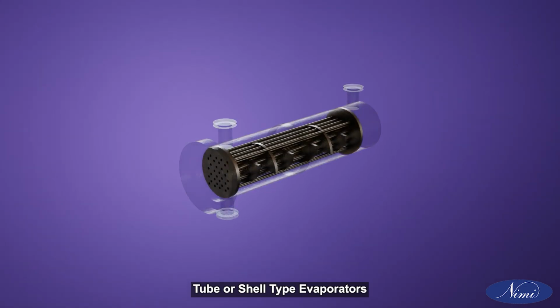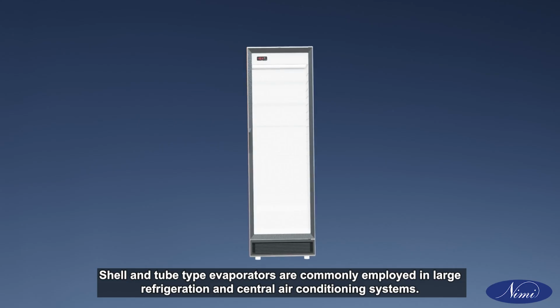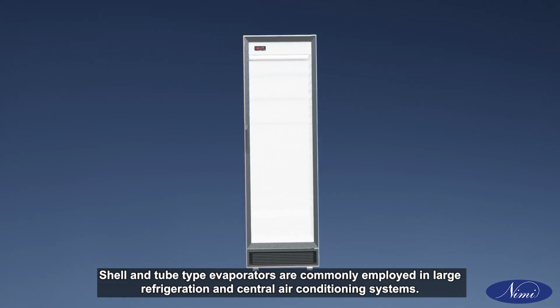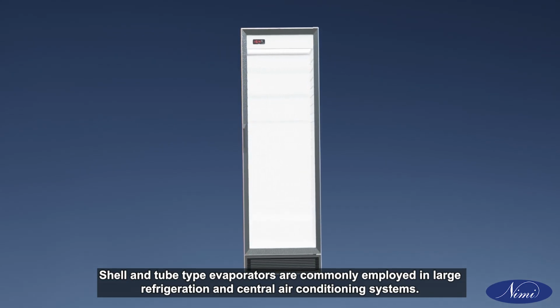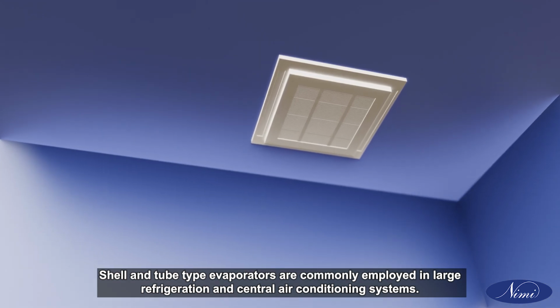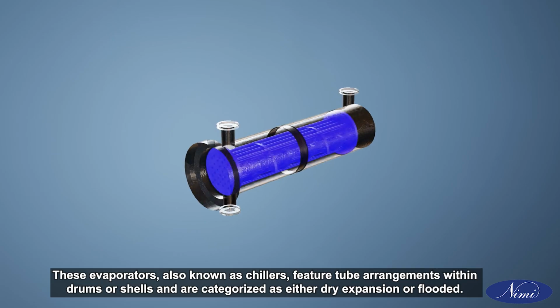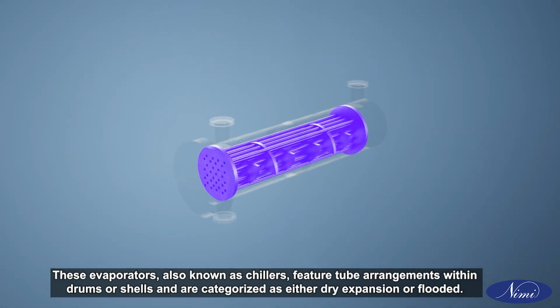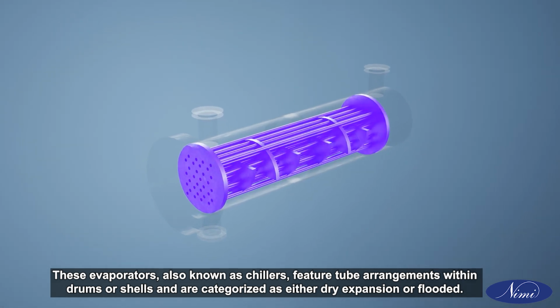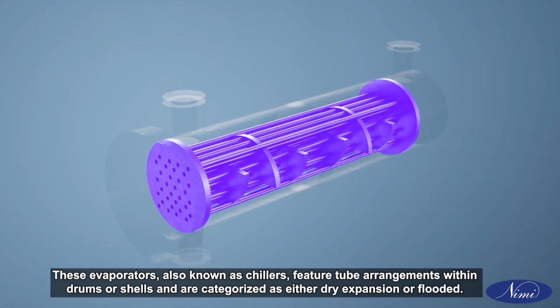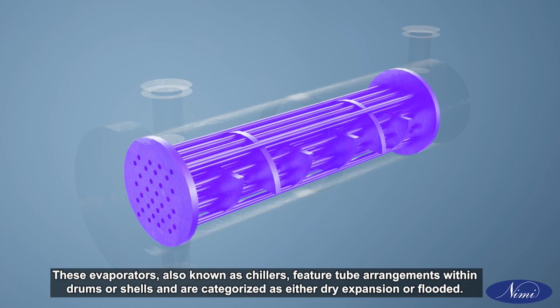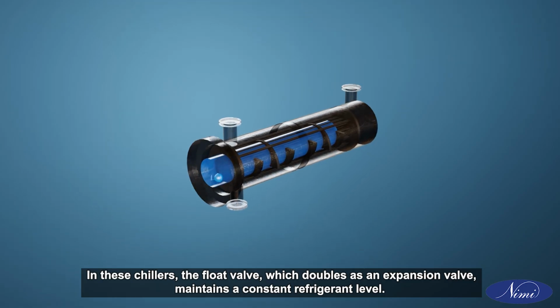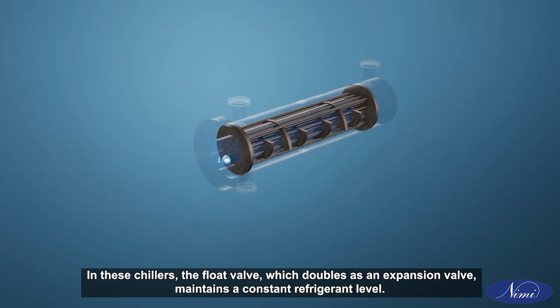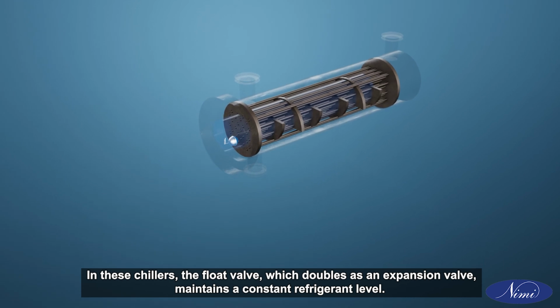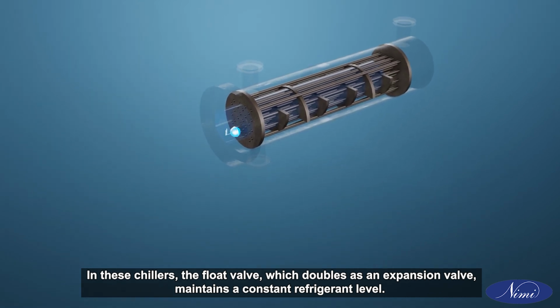Tube or shell type evaporators. Shell and tube type evaporators are commonly employed in large refrigeration and central air conditioning systems. These evaporators, also known as chillers, feature tube arrangements within drums or shells and are categorized as either dry expansion or flooded. In these chillers, the float valve, which doubles as an expansion valve, maintains a constant refrigerant level.